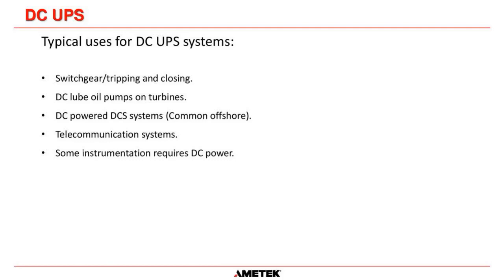DC powered DCS systems, very common offshore, where instead of using 120 volts AC to their DCS, their distributed control systems, they take 24 volts directly from a DC distributed system into their DCS. Telecommunication systems, they use positive and negative 48 volts DC, and some instrumentation can require DC power. So in all of these circumstances here, they're all things that you need to work when you lose AC power. When grid power goes away, you need the loads to carry on working.